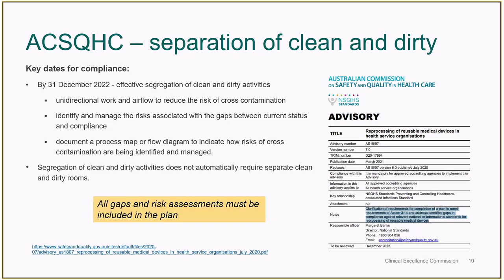The sorting, packing, and sterilizing can be in one area. You will still get that workflow and the airflow that is required. But if you had something like a transvaginal probe, where you're doing high-level disinfection in the medical imaging department, and it's not required to have the same air handling flows as a central sterilizing department, you can just segregate those clean and dirty activities in a defined workflow, so that you can determine where cross-contamination will or can occur.